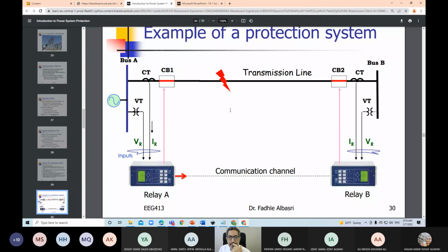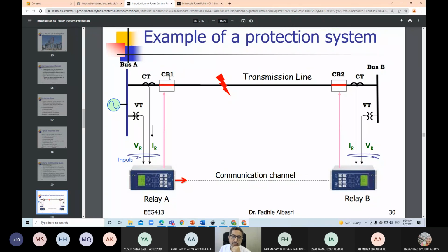Now, if a fault happens here, the current in the line will increase, and this relay will measure the impedance from this end to the fault point, and will compare it with the impedance of the line. Because the impedance has now reduced because of this fault, this relay will give a command to this circuit breaker. It will open the fault from this side. So there will be no current flowing from this side once breaker 1 is open. However, there will also be a current fed from the other end. So this fault is not cleared unless the other breaker is opened.